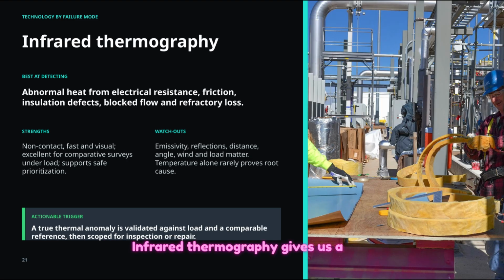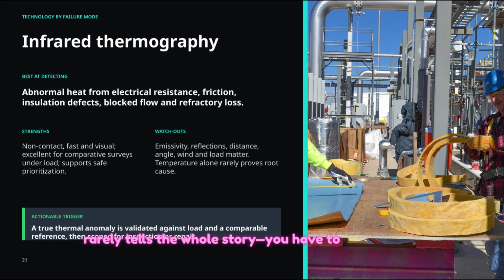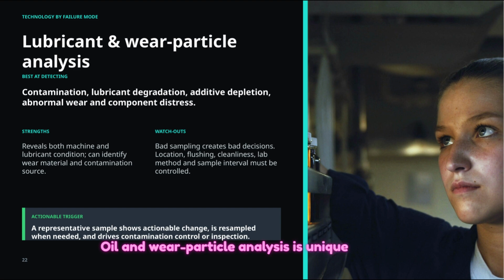Infrared thermography gives us a fast, non-contact visual of abnormal heat. It's the standard for electrical surveys. The watch out here is that temperature alone rarely tells the whole story. You have to account for emissivity and load. A hot connection on a motor running at 10% load is much more serious than one at 100% load. Oil and wear particle analysis is unique because it tells us about both the machine and the lubricant itself. It can identify the exact material that is wearing away. The biggest risk here is poor sampling. If your sample is contaminated during collection, you'll end up making very expensive, very wrong decisions.